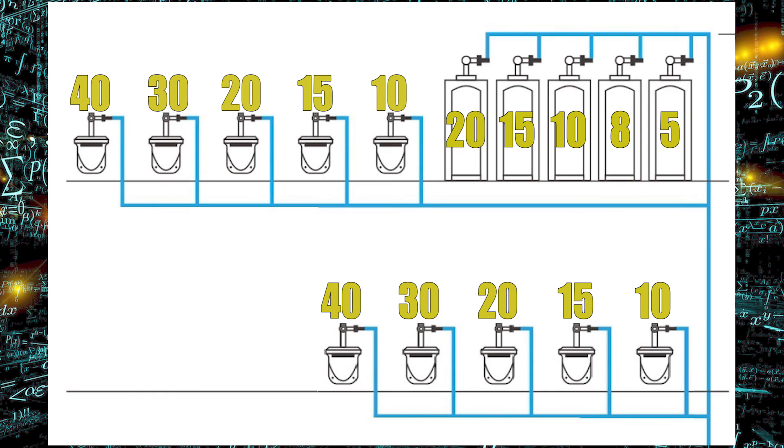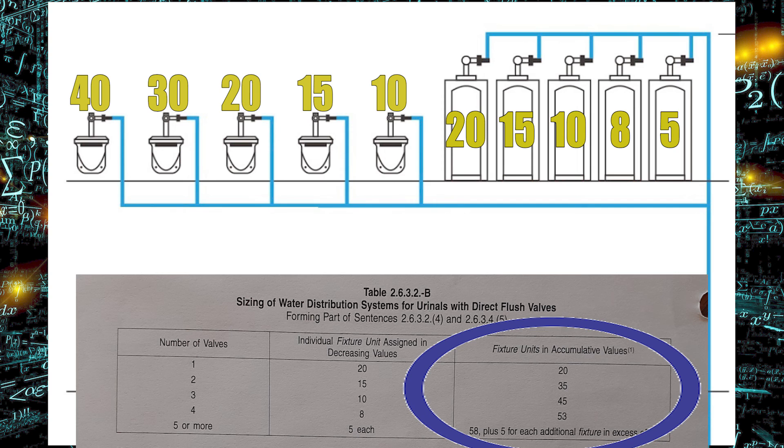Now let's look at the fixture units between the urinals. So between urinals two and three there, we're only supplying the first two, we are at 35 fixture units. I move over to the right, there is 45 fixture units right here, and between here is 53 fixture units, and then the pipe that drops right down through the bottom of the floor, 58 fixture units. Notice how I just read the fixture unit load that is in the right-hand most column in table 2632B. That's what those numbers are there for.